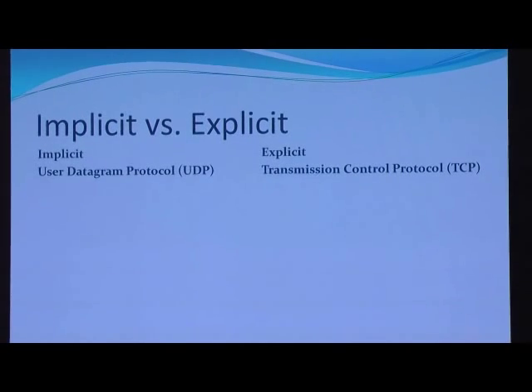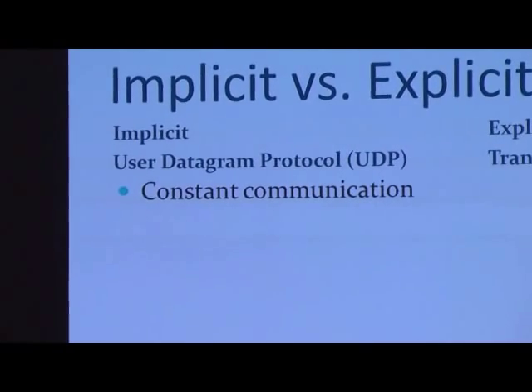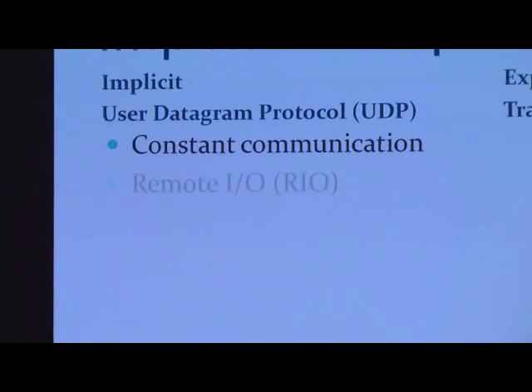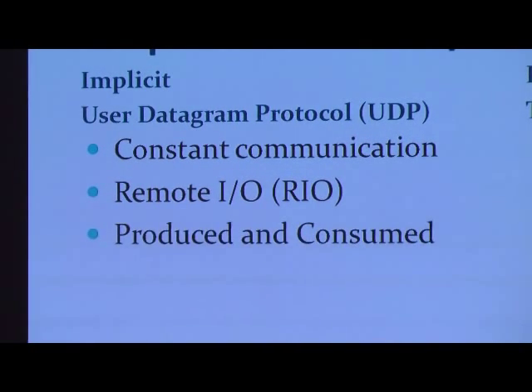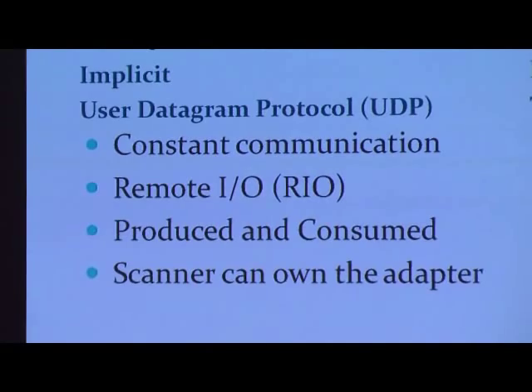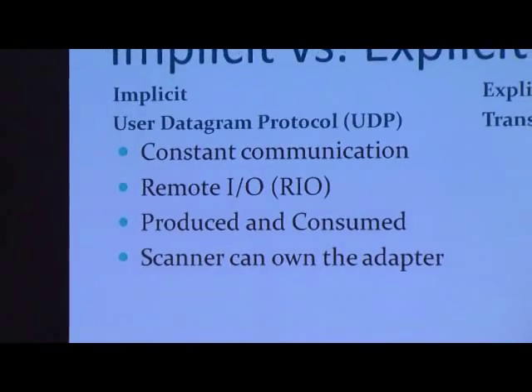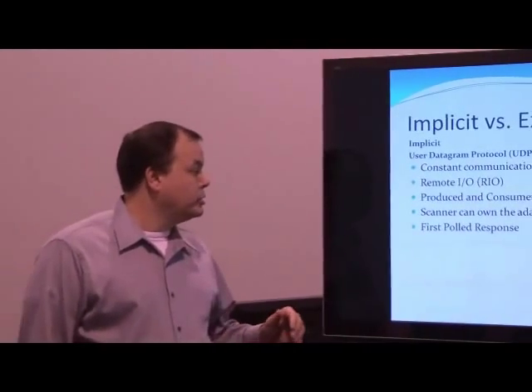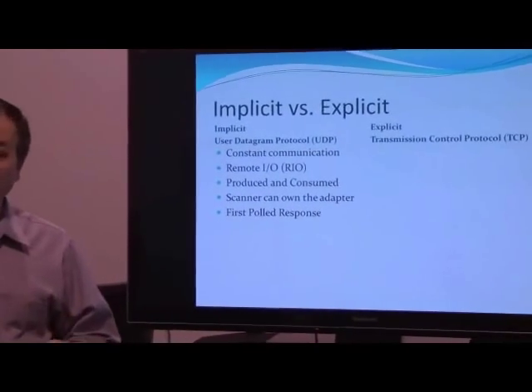First, let's talk about implicit messaging. It uses the User Datagram Protocol, or UDP, and it is a constant, continuous connection between the Ethernet IP adapter and scanner. A common form you'll probably see is a remote I/O connection or, for Rockwell products, the producer/consumer tags. In this model, the scanner owns the adapter — the adapter looks for a first-poll-response master in order to communicate.